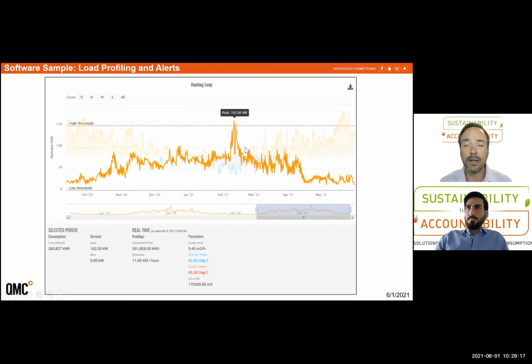And drilling in further, even to any meter, this is where you can really see the power of interval data. This is an example of a thermal meter on a heating loop. What we're showing here is the interval data for about a 7-8 month period. You can see a lot of information here, the orange being the total consumption of that meter over this period. We've set, in this case, a threshold of 150 kilowatts to trigger an alarm if the consumption of the meter ever hits that point. You can also see in the background here heating and cooling degree days, with days over 0 degrees, and in light blue, days that are under 0 degrees. So you can see that correlation of heating use versus weather right in one spot.